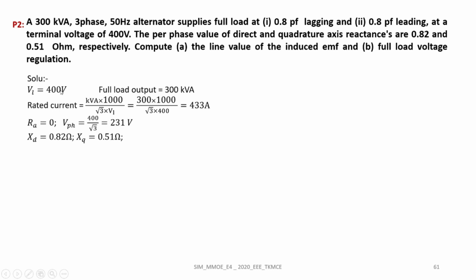Coming to the solution, here the line value of the voltage is given as 400 volt and full load output is 300 kVA. So from this line value and this kVA rating, we can calculate the rated current, and rated current is obtained as 433 ampere. And after converting this line value into phase value, the phase value is obtained as 231 volt. And here XD is given as 0.82 ohm and XQ is given as 0.51 ohm.